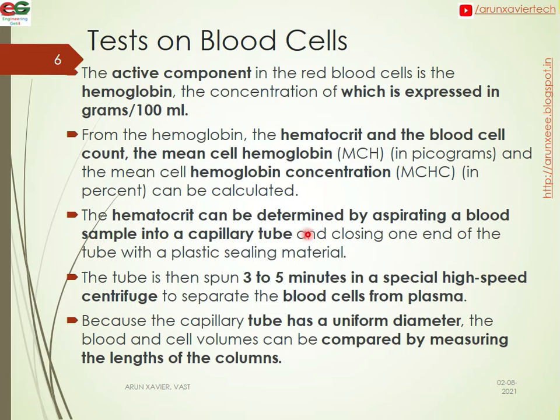The hematocrit can be determined by aspirating a blood sample into a capillary tube and closing one end with a plastic sealing material. This tube is spun for 3 to 5 minutes in a special high-speed centrifuge to separate the blood cells from the plasma. Because the capillary tube has a uniform diameter, the packed cell volume can be determined by measuring the length of the column.